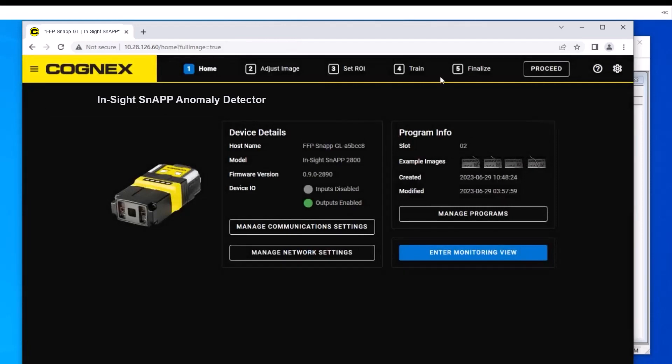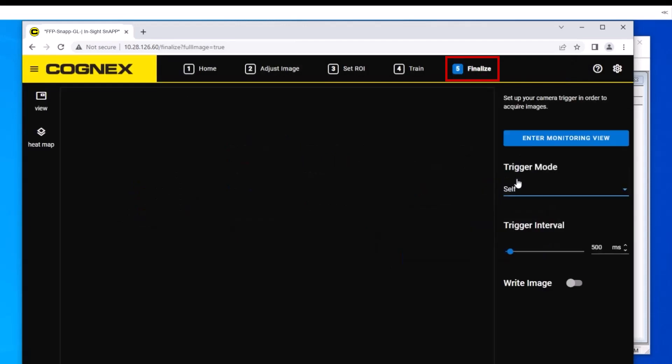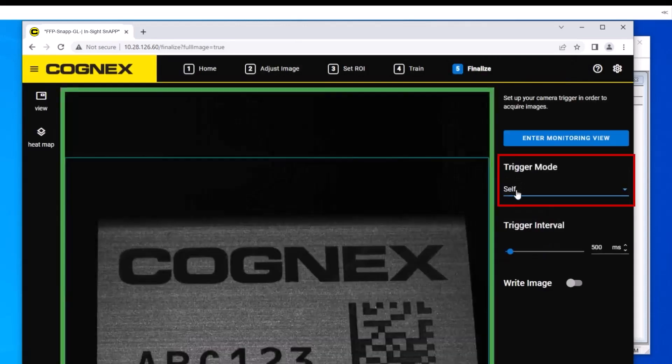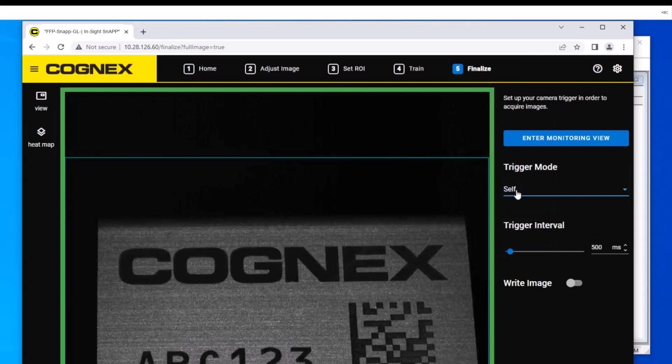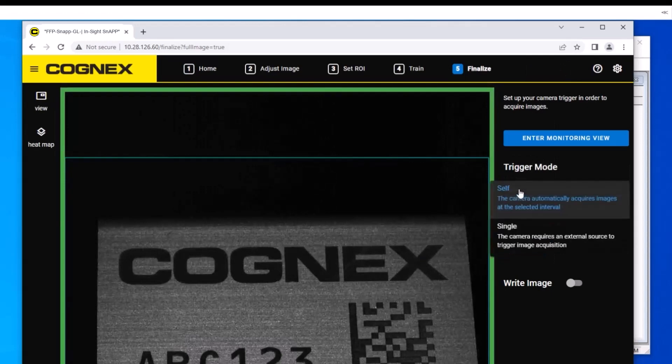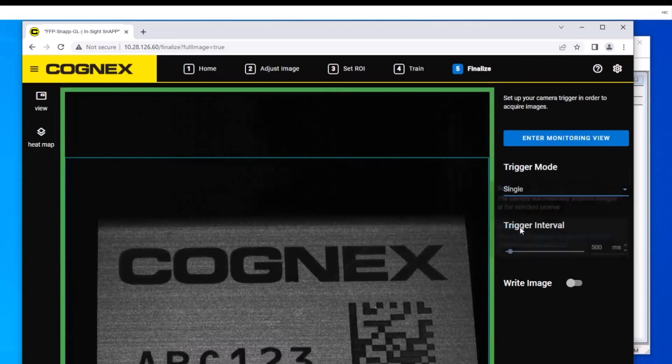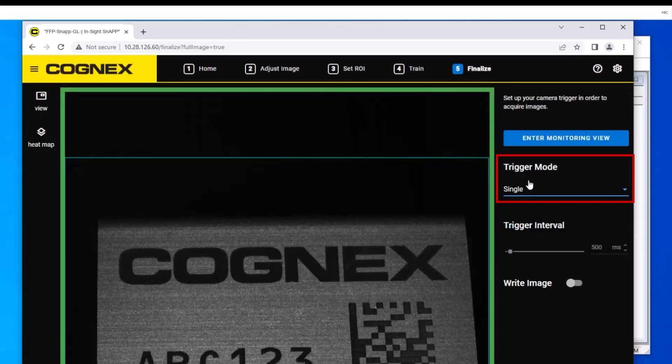The final step is to change the trigger type from self to single trigger for the PLC. Navigate to step 5, finalize tab to set the trigger. The default trigger type self will trigger the In-Sight SnAPP. The single trigger will trigger from an external source, such as the PLC or a discrete input.